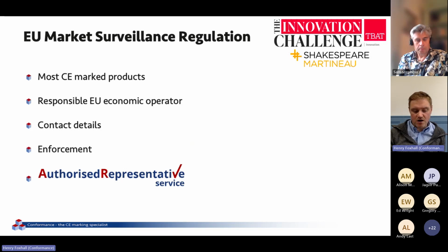And as we've explained, if you are a UK manufacturer wanting to sell into Europe, you will need a European address. And that can be a sister company, it can be a sub-part of your own company, but as small entrepreneurs and SMEs, the likelihood of you having a European address is quite small. So you may want to employ a third party to be that European address for you. We have a sister company called Authorised Representative Services. If you contact them with a product that you want to place on the market, they will provide you with a European address and they will hold your technical file for you. The only thing they ask is that they audit that technical file first to check that it meets the requirements of the legislation you claim that it does. And there'll be an ongoing fee for that.